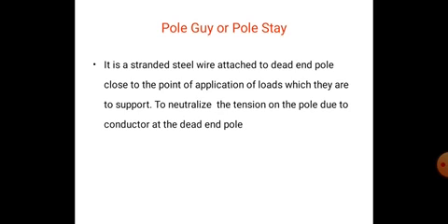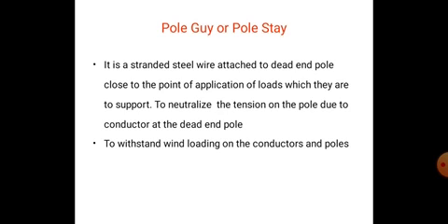It is a stranded steel wire attached to dead end pole close to the point of application of loads which they are to support, to neutralize the tension on the pole due to conductor at the dead end pole, to withstand wind loading on the conductors and poles, and to keep the pole straight without bending.